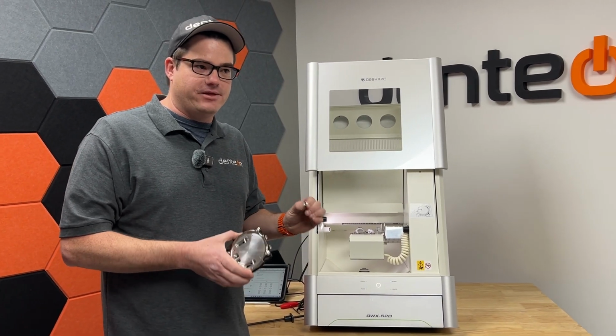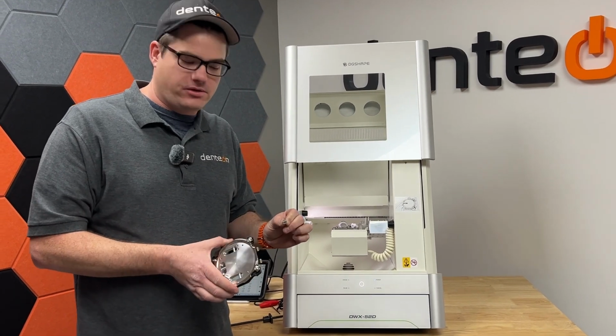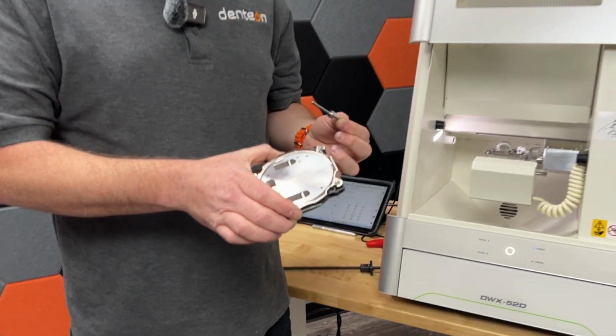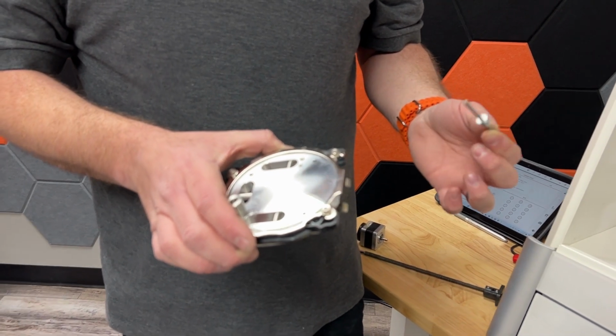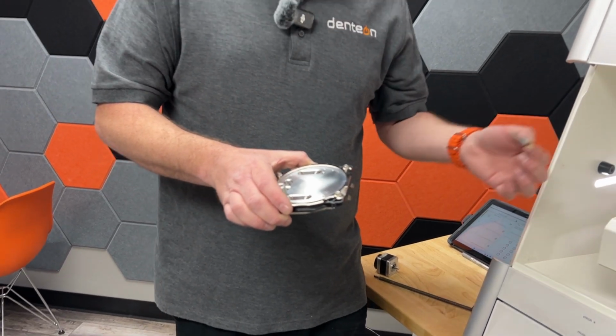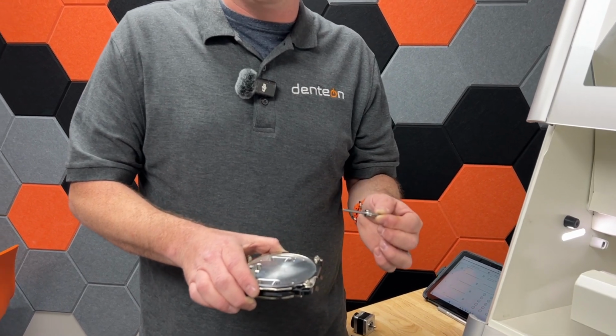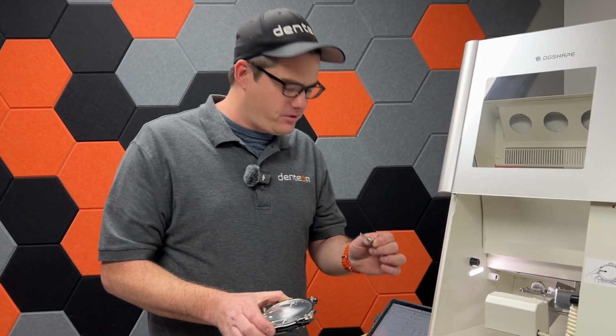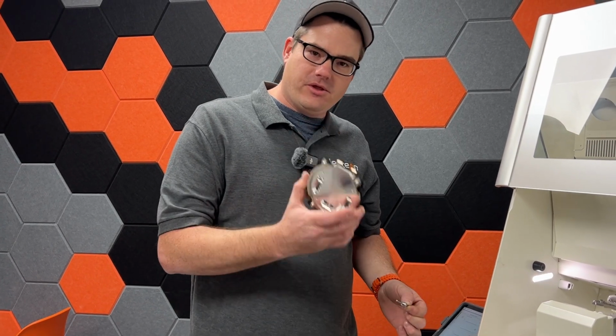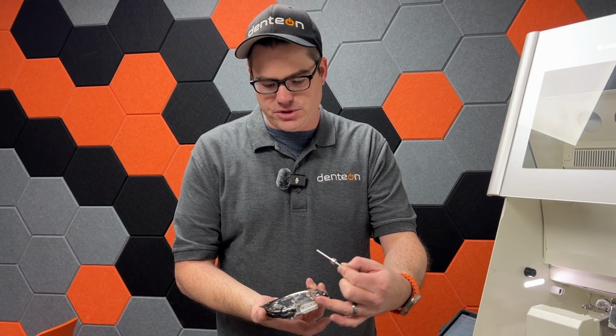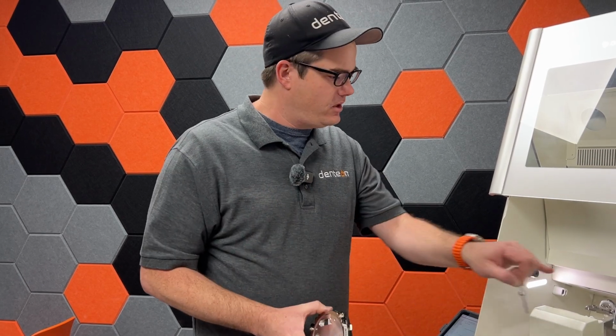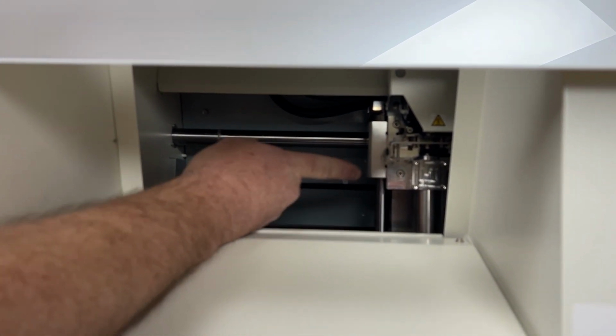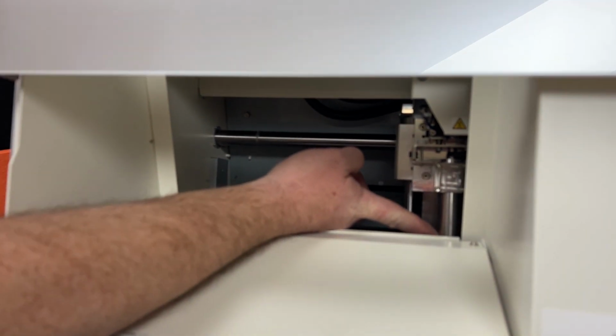Okay, so the first thing with calibration is absolute perfect surgical cleanliness. The machine uses an electronic signal to touch itself. Anything that doesn't conduct electricity, like maybe zirconia or wax or PMMA, the things that we cut, can disrupt the accuracy of that calibration. So the word is surgical clean, no fingerprints, wipe it down with alcohol and a clean rag. This pin must be perfectly clean. This must be perfectly clean, especially on the points where it touches the machine and where it's measuring itself. Everything's perfectly clean. We're perfectly clean here on these datums here on the tool carriage. We're perfectly clean in here on the spindle, on the top of the spindle. There's a small leaf spring that also must be perfectly clean. And the collet must be recently serviced and perfectly clean.